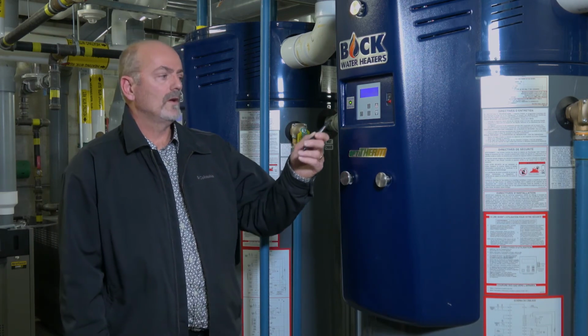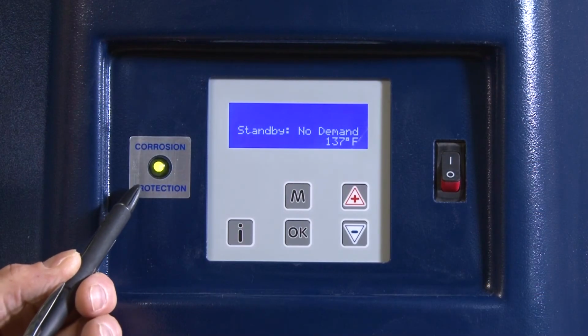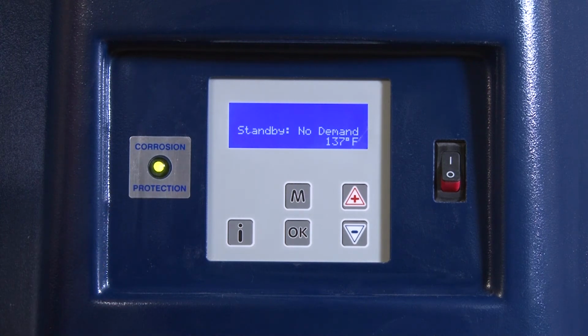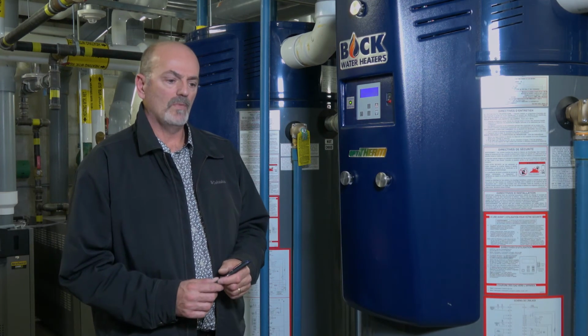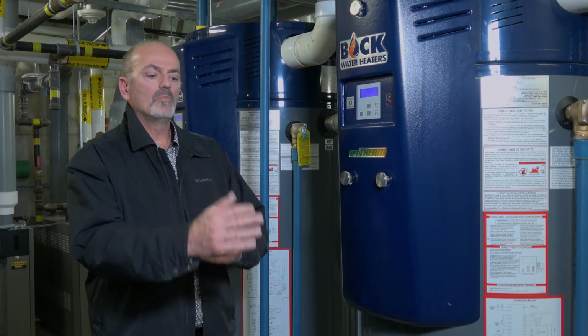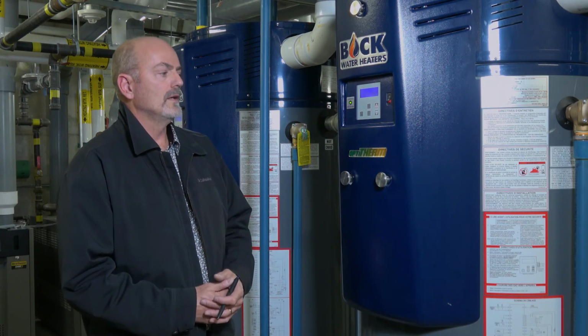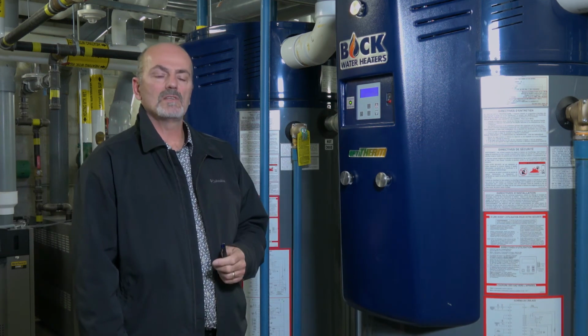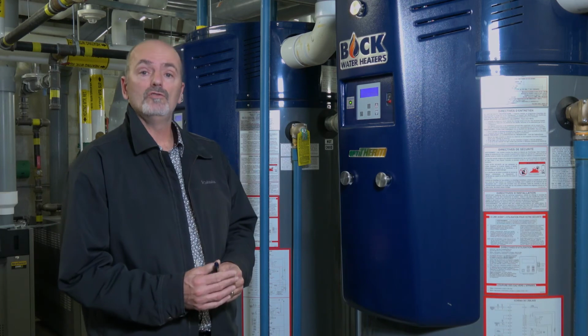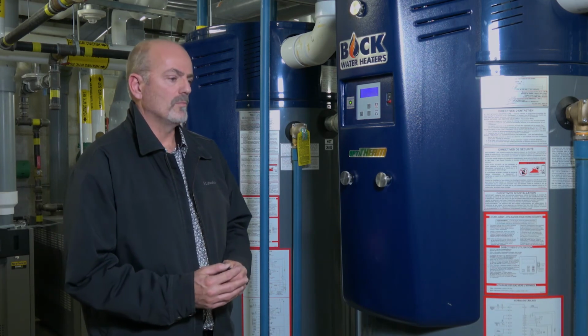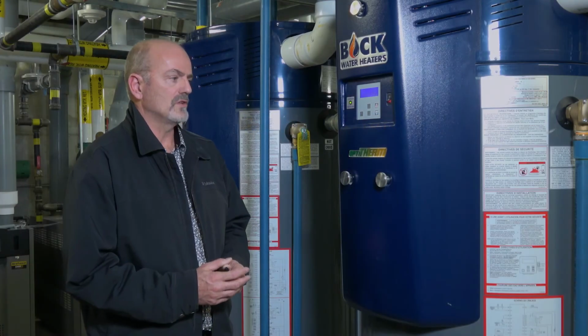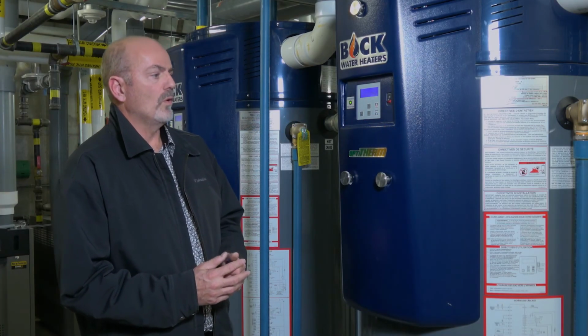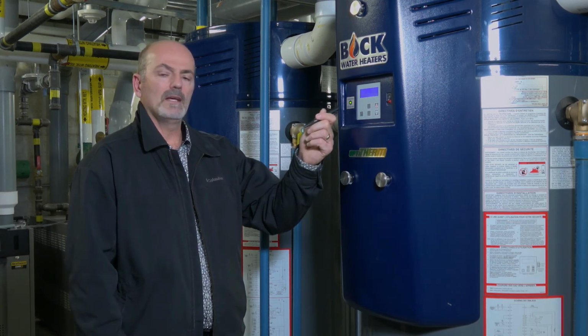There is on here one item that says corrosion protection, the green light. Each tank is equipped with electronic cathodic protection. It's an automatic cathodic anode rod, where a small millivoltage goes across and protects and works like an anode rod. If this ever turns red, that means it's not working. That means you do not have protection from excessive corrosion and corrosion of the tank through electrolysis. So it's necessary to shut the heater off and get this addressed.